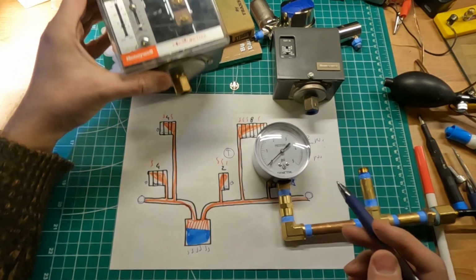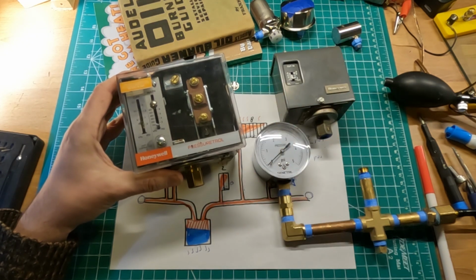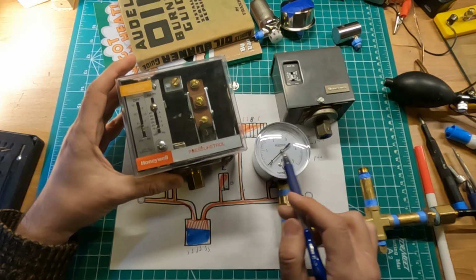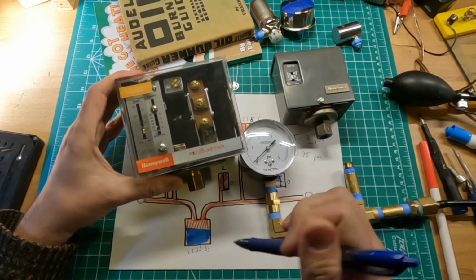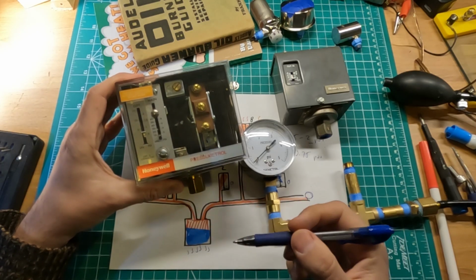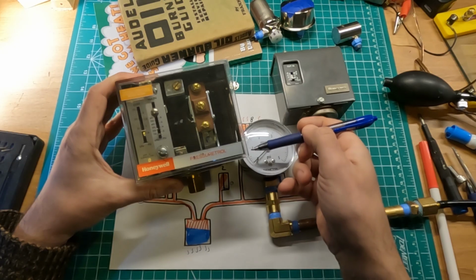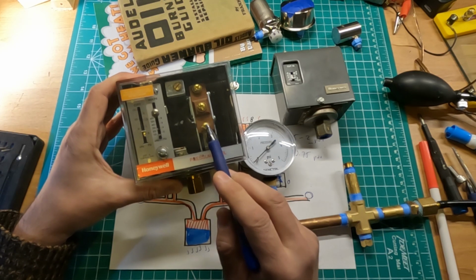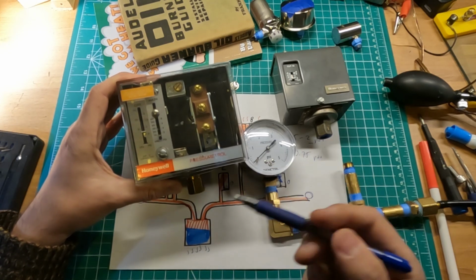In theory, you could try to set those devices to shut down your boiler at let's say the proverbial 0.75 psi. The problem with that is that they are not precise enough devices, and you will notice that when the pressure falls down, the switch might not be precise enough to allow the flow of electricity so that the boiler restarts again.